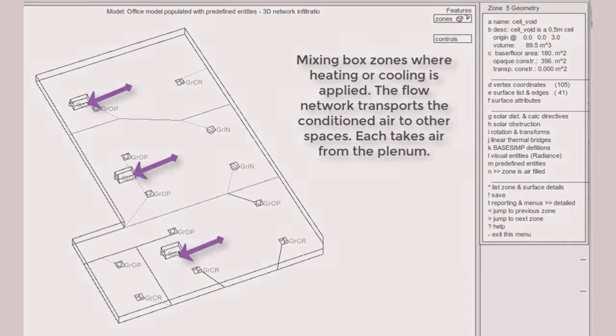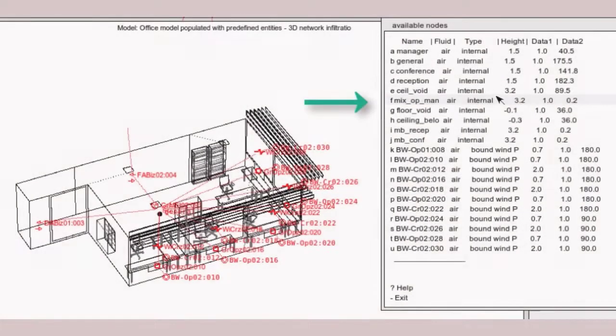In the context of ESPR, I have often used thermal zones and flow networks to represent mixing boxes, ducting, and flow paths as a prelude to the transition to system components. To use virtual air movement to represent physical air movement has a pleasant symmetry. An example is the mix of spaces in this office model with mixing boxes in the ceiling void that are controlled to deliver specific temperatures and humidity, and then we let the air flow network take care of the delivery and return of the air.